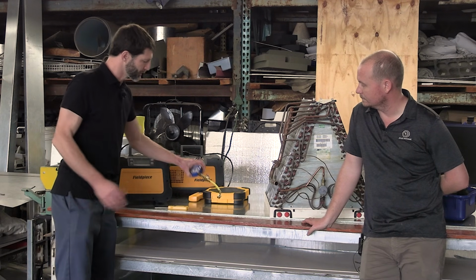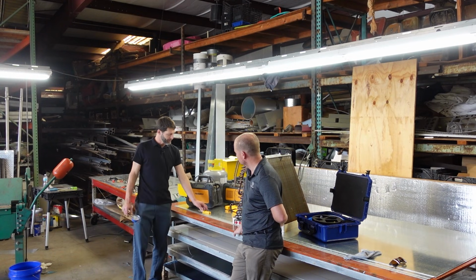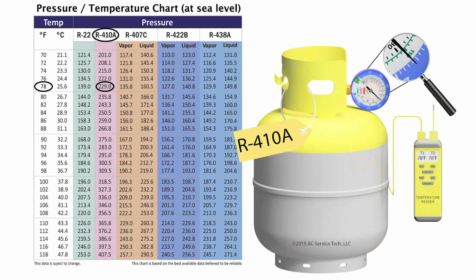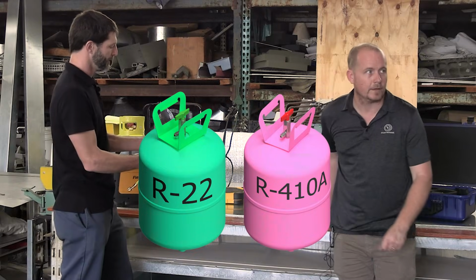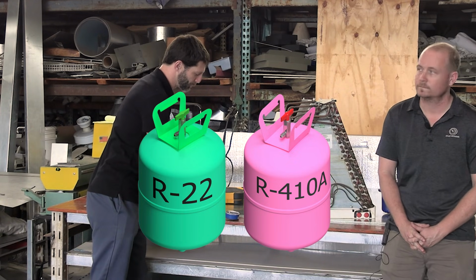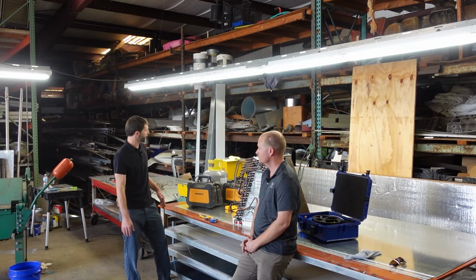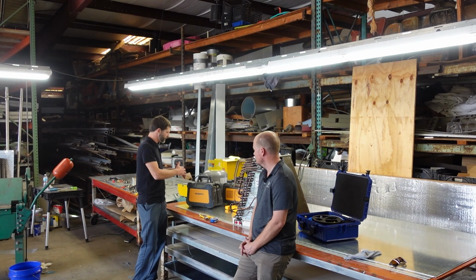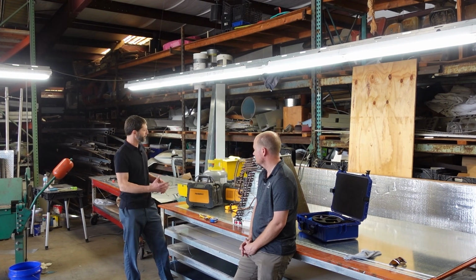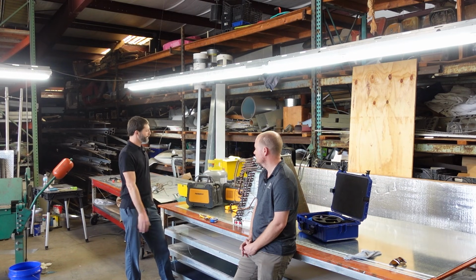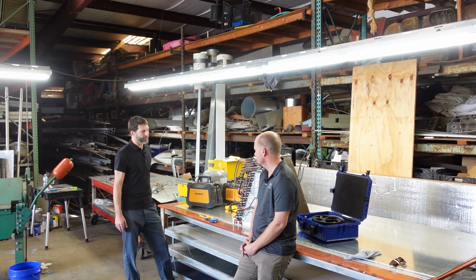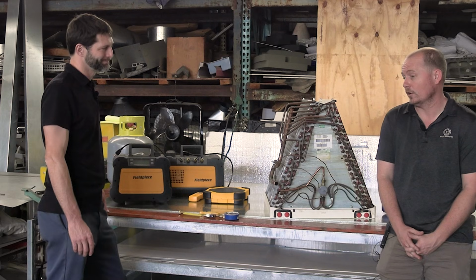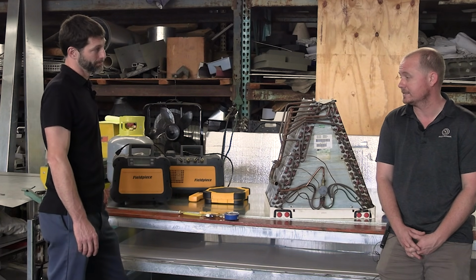So you'd go ahead and hook your gauge up to the tank, and take a temperature reading of the air or the actual tank itself in order to basically match the saturated temperature on your gauge or PT chart to the temperature surrounding the tank. That's how you know what refrigerant it is, if it's R22 or if it's R410A or whatever the refrigerant is. So you've got to make sure that you're not mixing refrigerants, because that's no good. You're not going to be able to end up reclaiming that at the factory. So yeah, it's costly, and also we're not supposed to mix them based on EPA standards.